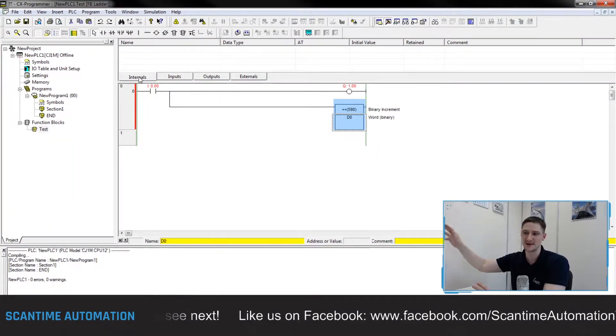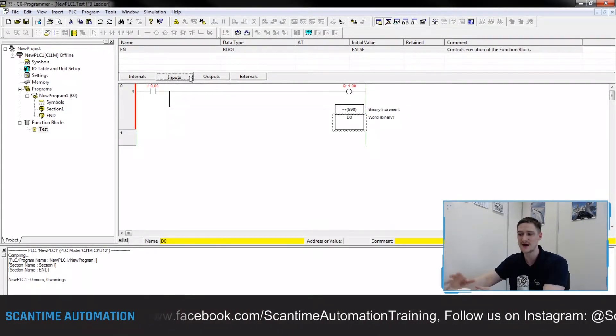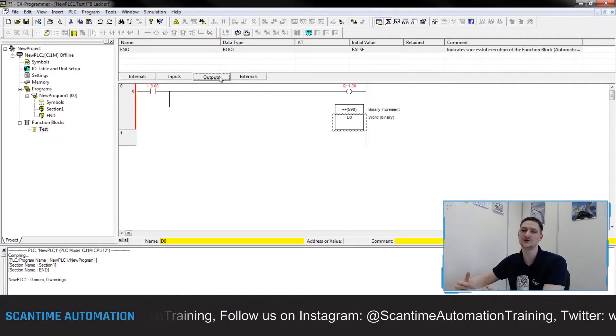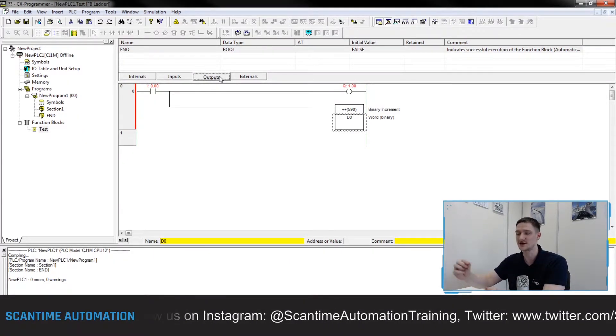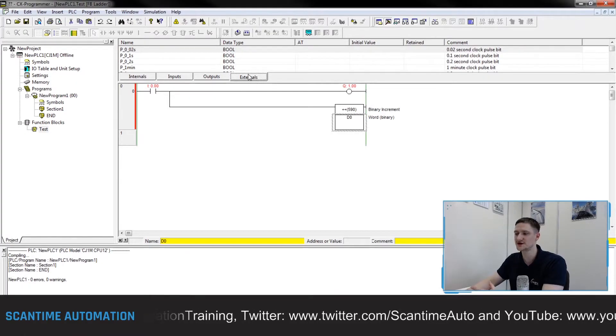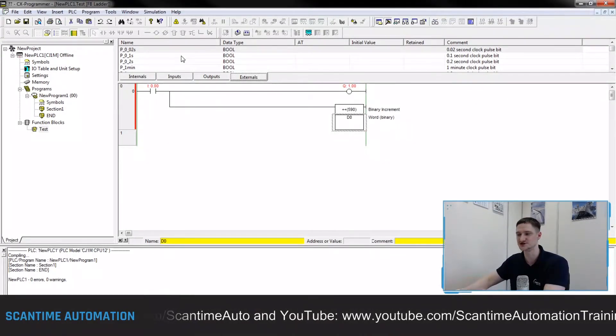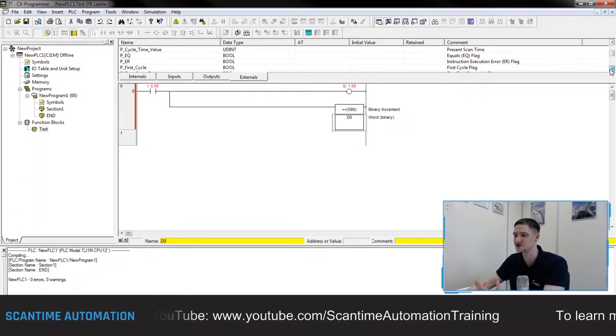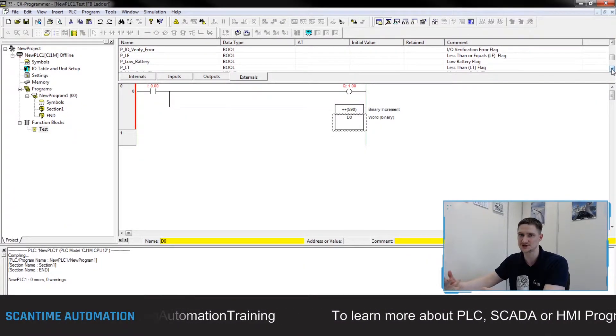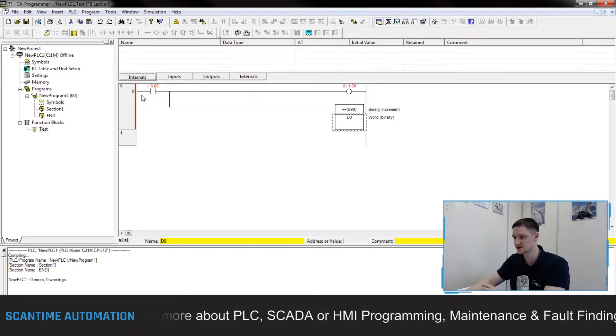To fix this, we use the internal addressing area at the top of the function block. There are several tabs: Internals are signals that exist only inside the block — contacts or coils internal to the function block. Inputs are read-only signals — contacts sent from the main program into the function block. Outputs are write-only signals used as coils inside the block, sent out to the main program. Externals are general bit addresses already created by the PLC, such as clock pulses, always-on, always-off, and first-cycle flags.